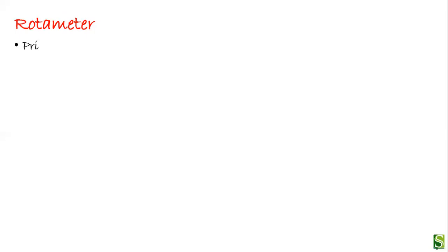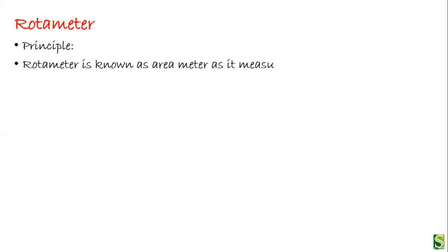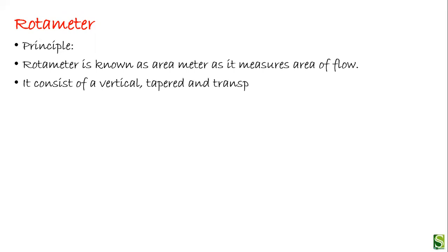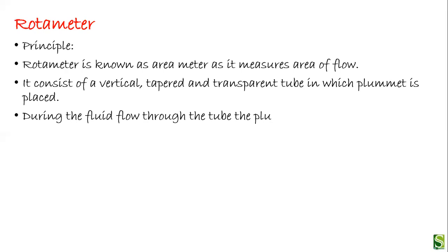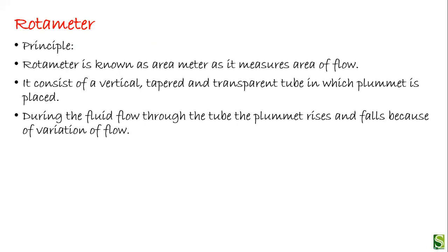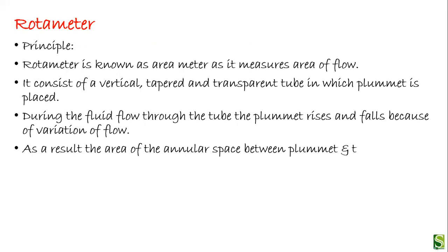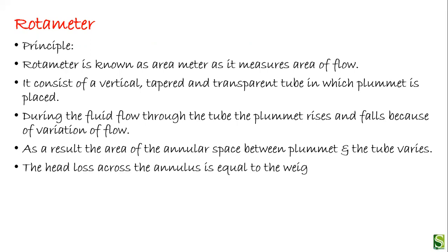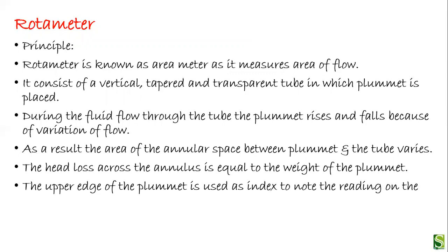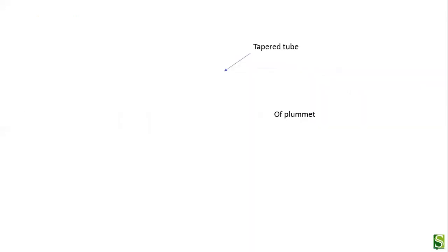Now we move to the rotameter. Its principle: the rotameter is also known as an area meter as it measures the area of flow. It consists of a vertical, tapered, and transparent tube in which a plummet is placed. The plummet is free to move as the velocity of the fluid increases or decreases. During fluid flow through the tube, the plummet rises and falls due to variation in flow, varying the area of the annular space between the plummet and the tube. The head loss across the annulus is equal to the weight of the plummet. The upper edge of the plummet is used as an index to note the reading on the tapered tube, and this value indicates the flow of the fluid.